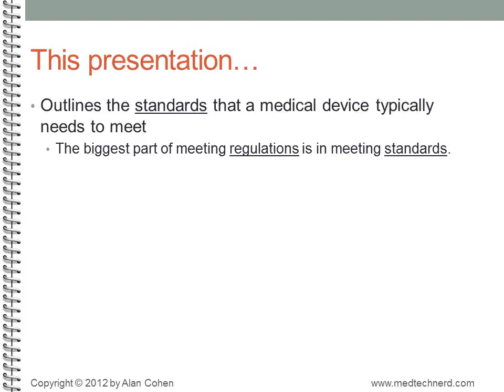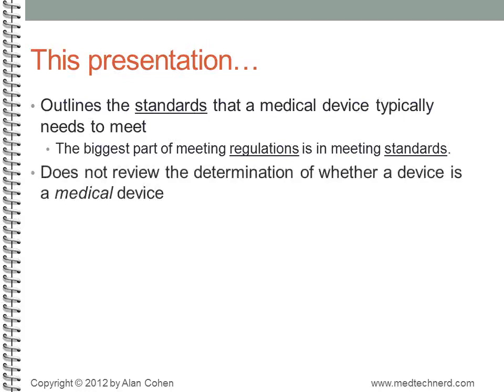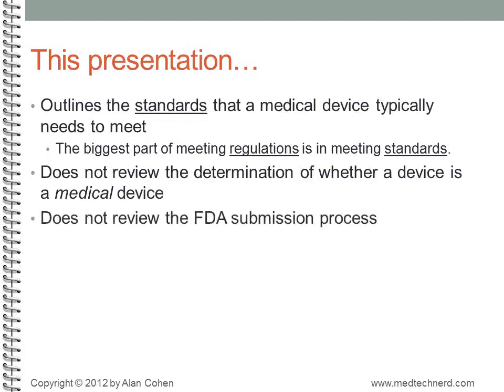Note that we'll be covering standards rather than regulations. For most medical devices, most regulations actually involve meeting internationally accepted standards. Those standards are what we'll be focusing on. We won't, for example, review the process of determining whether a device is actually a medical device and thus subject to regulation by the FDA and similar international bodies. Nor will we be reviewing the process for submitting an application to the FDA.